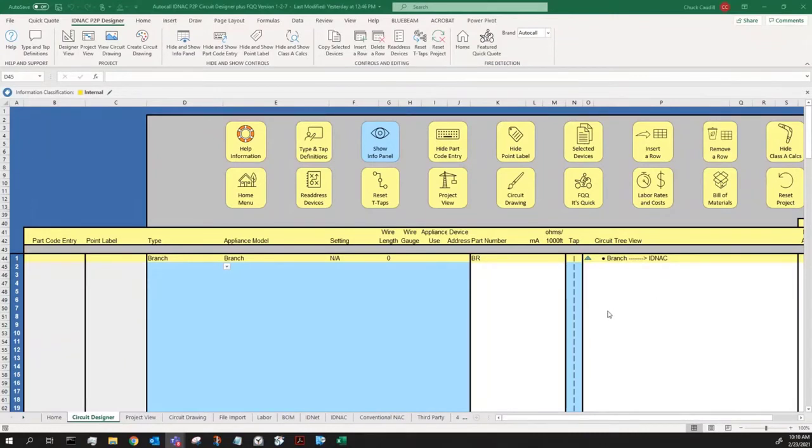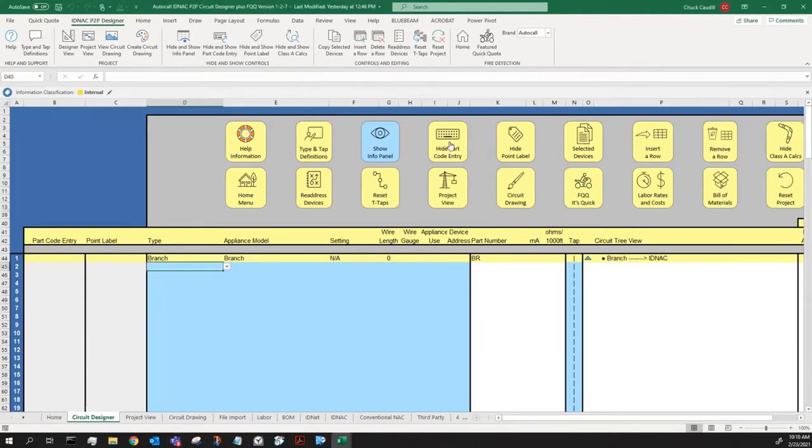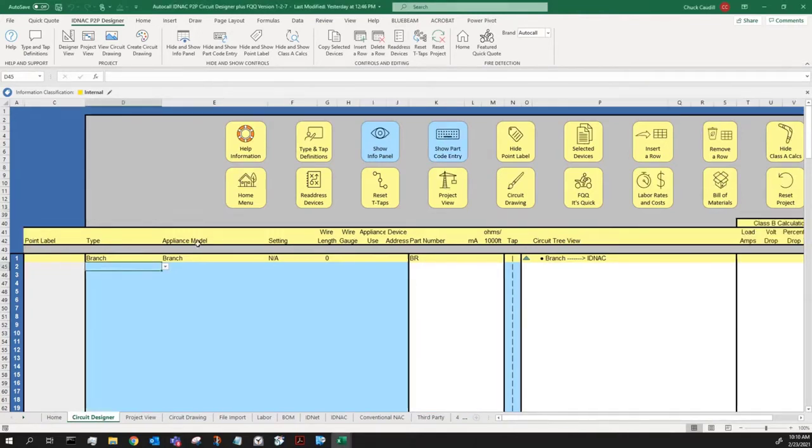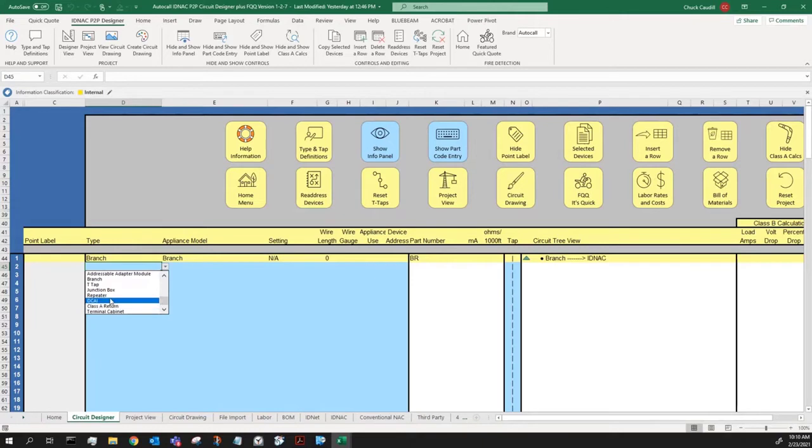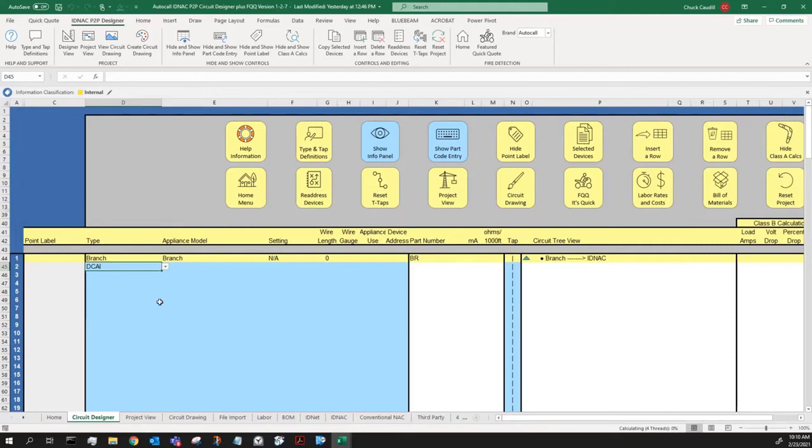In this exercise, we're going to use the IDNAC circuit designer to build a Class A circuit. The first thing I want to do is start with a DCAI card. What that does, that splits the IDNAC channel into a feed and return, both starting with 29 volts, that will feed out to field wiring.